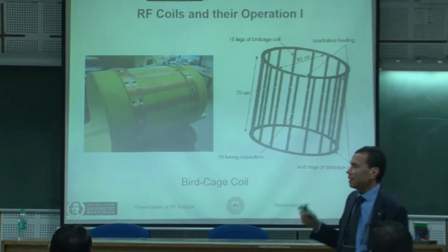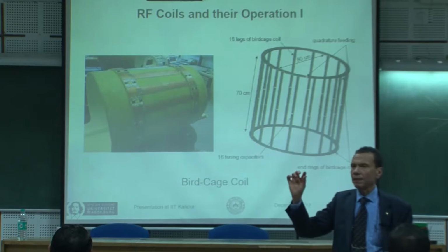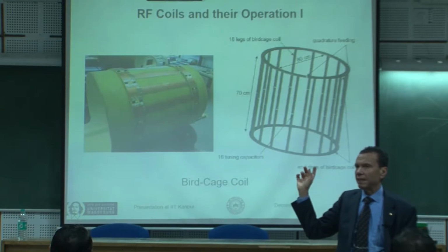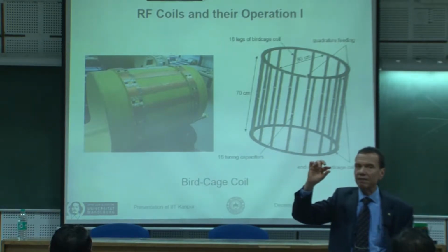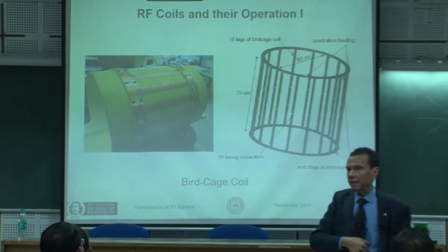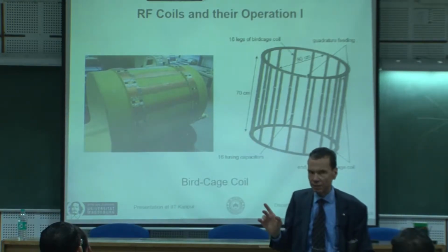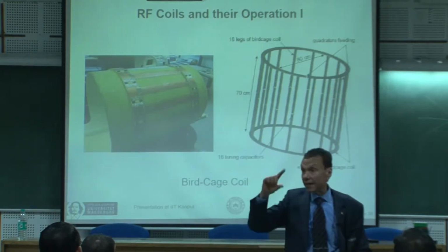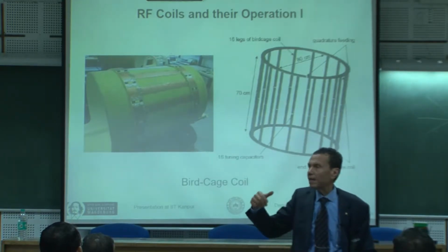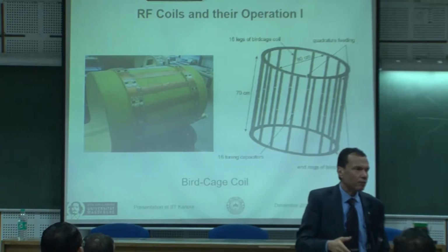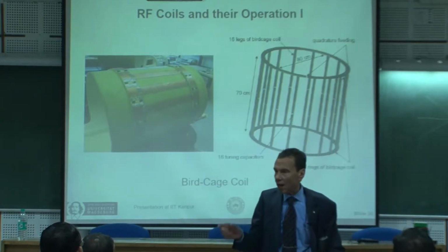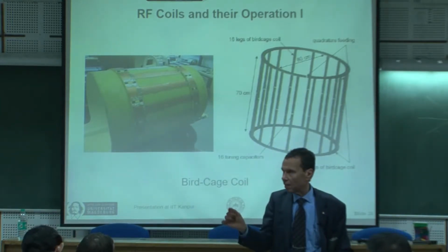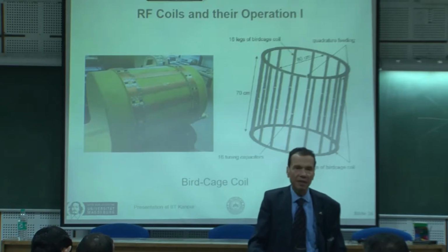I would like to discuss maybe at the beginning the bandwidth of the coil. You have already seen that the bandwidth itself dictates the thickness of the layer in the transmission regime now; I will come back to the receiving regime. The thickness of the layer, or the resolution in the z direction, is determined by the bandwidth of the exciting signal. One of the factors affecting the bandwidth is for how long you expose. You have limited time, so this is a must. So the bandwidth depends on the time of exposure.